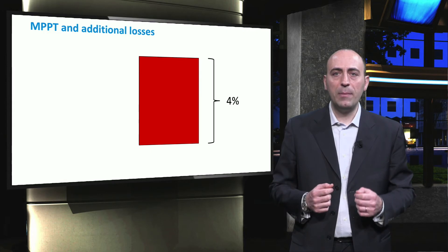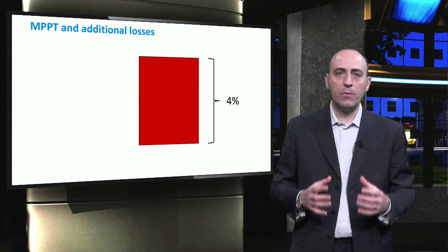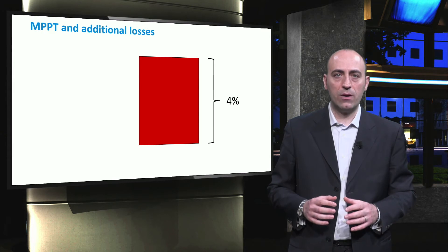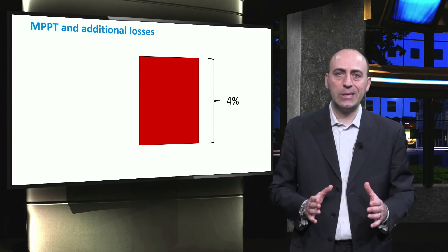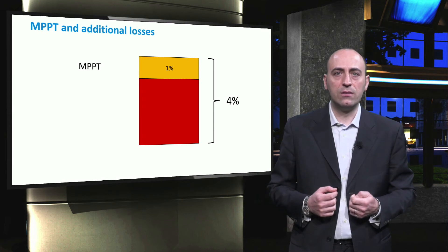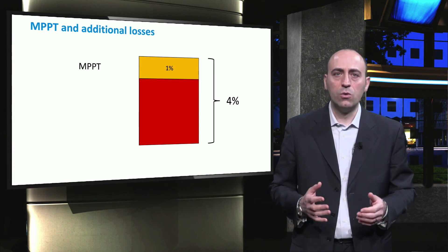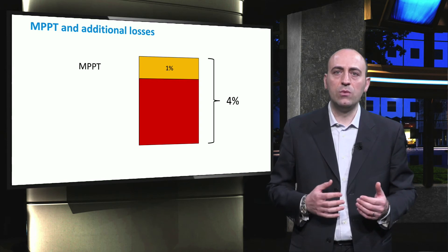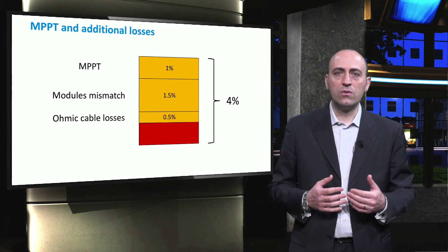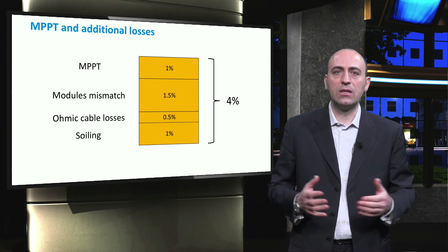The efficiency of the MPPT is not included in the SNL performance model. This is because the efficiency of most maximum power point trackers used in the inverter ranges between 98 and nearly 100% at every level of input DC power, and the voltage provided is always within the accepted minimum and maximum window for the MPPT to work correctly. A deduction of 1% in the system performance has therefore been used to take the MPPT losses into account. Among other losses worth mentioning: mismatch between modules, which accounts for 1.5%; ohmic losses related to external cabling of the inverter, usually considered to be around 0.5% if not determined analytically; and soiling losses as an additional loss of 1%.